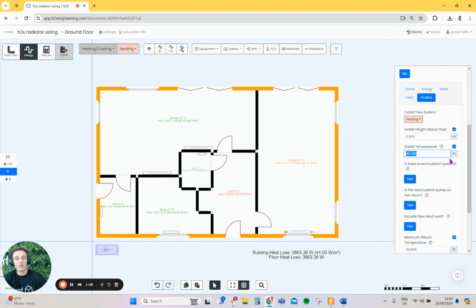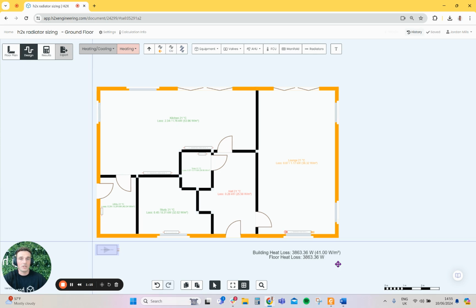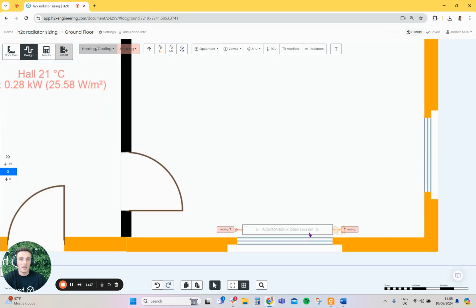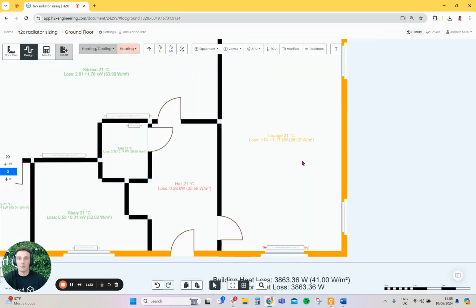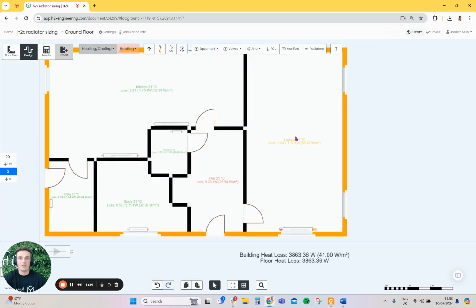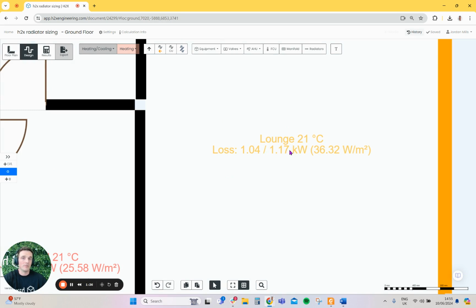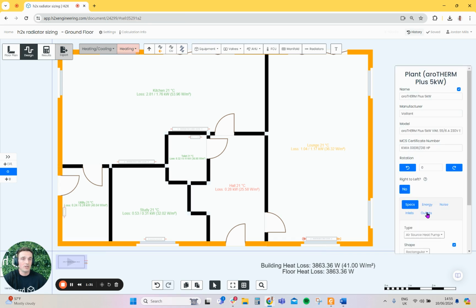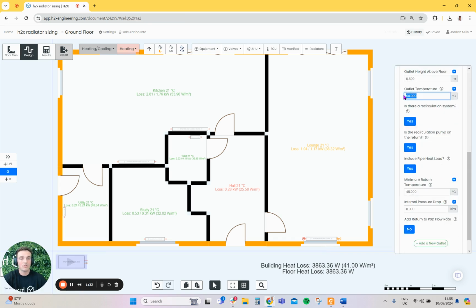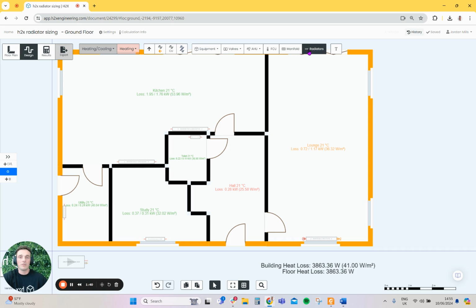So you don't have to connect that up, but if you come along and change that at the heat pump, so if we say increase this to a 50 flow and a 45 return, what you'll see is that same radiator, the output goes up. It was around 0.7 kilowatts, now it's just over 1 kilowatt for the same radiator. It still doesn't satisfy the heat demand of the room, which is 1.17. So I'll return that back to how it was, and just continue with the other radiators.